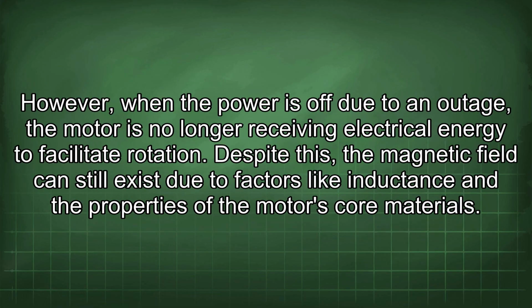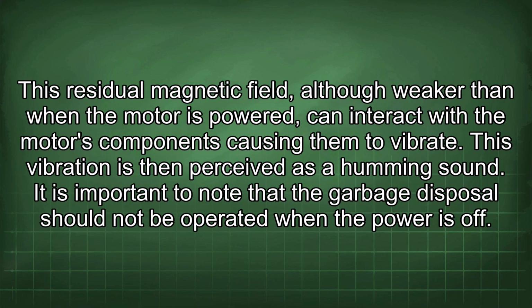However, when the power is off due to an outage, the motor is no longer receiving electrical energy to facilitate rotation. Despite this, the magnetic field can still exist due to factors like inductance and the properties of the motor's core materials. This residual magnetic field, although weaker than when the motor is powered, can interact with the motor's components, causing them to vibrate. This vibration is then perceived as a humming sound.